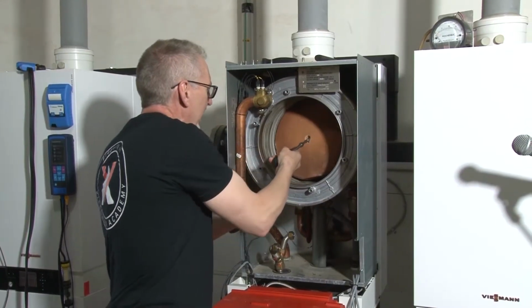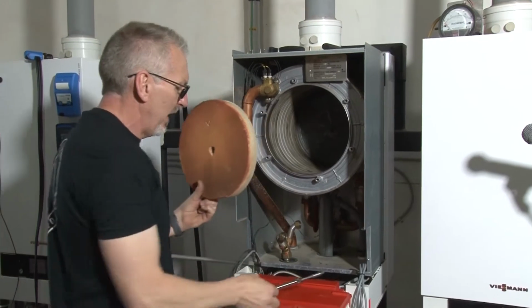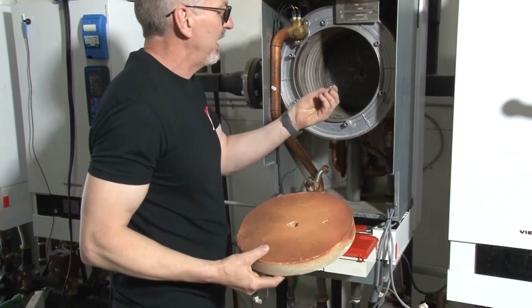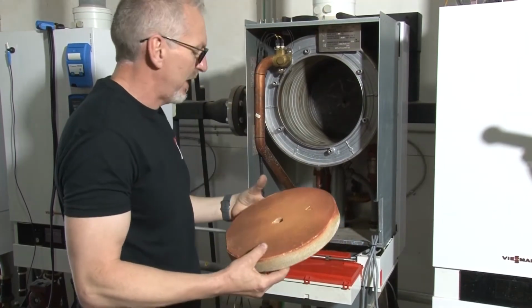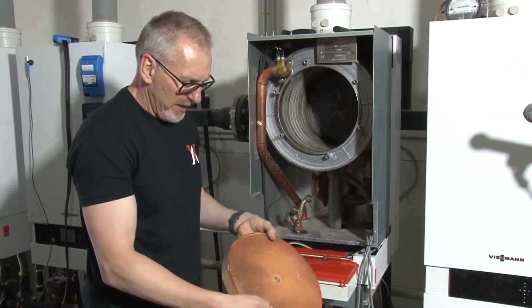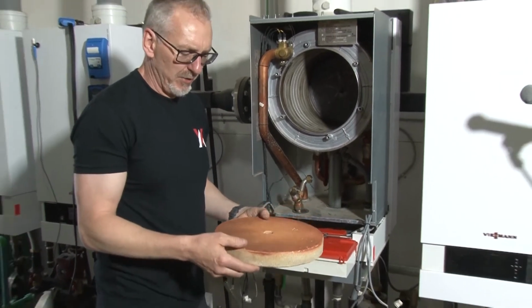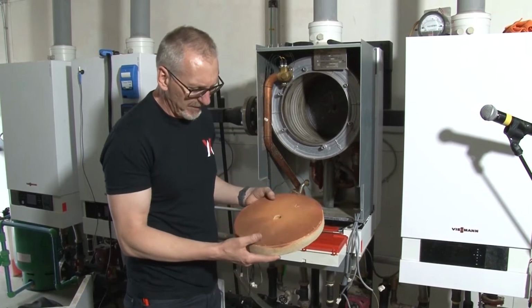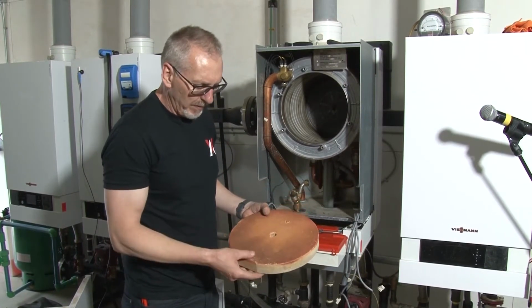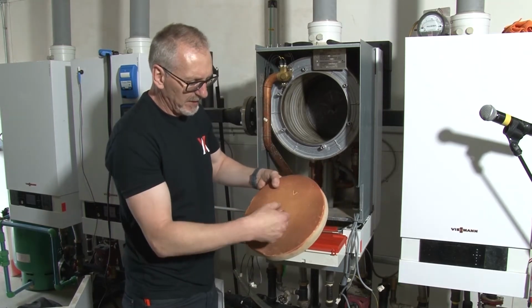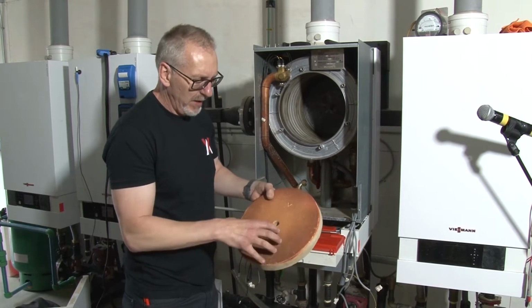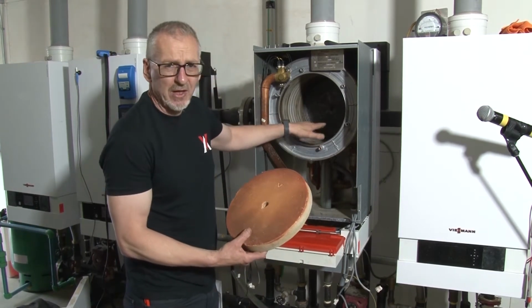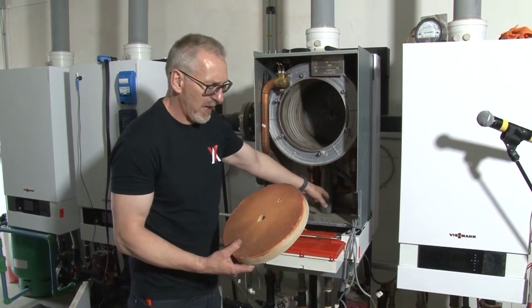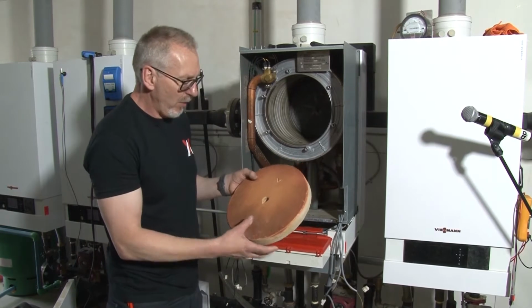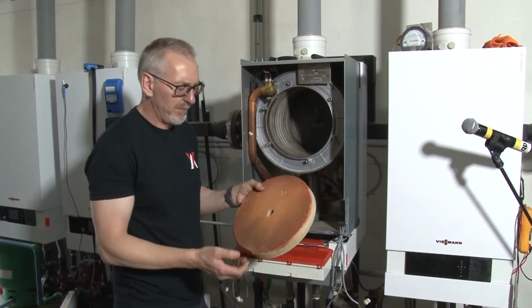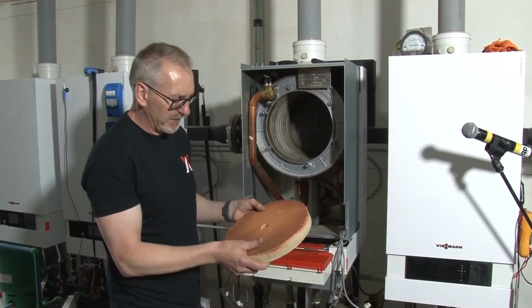So I usually stick the screwdriver in there and I can pull that refractor out ahead of me. And what I'm doing here basically is, again there's a nut and a washer there I want to make sure I don't lose, I'm looking at the condition. So your boiler heat exchanger here, the fire side, tells you a lot of information. There's a lot of stories this little refractor is telling me. Has it been hit with water? If I see a tide mark on the heat exchanger that's dried off, I see a lot of flaking and debris, then I know that heat exchanger basically had a backup of condensate inside of it, which tells me that the condensate here is either slowly draining, I got some plugging in the pipe here, or it's completely blocked, and of course that's maybe why you're there servicing it, because you've got a fault issue with the boiler.